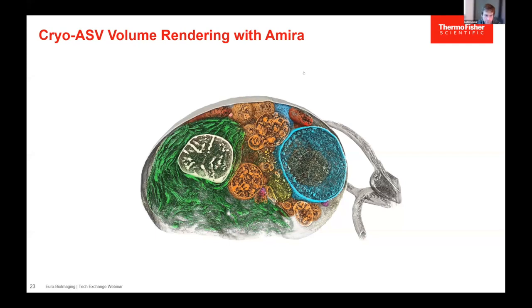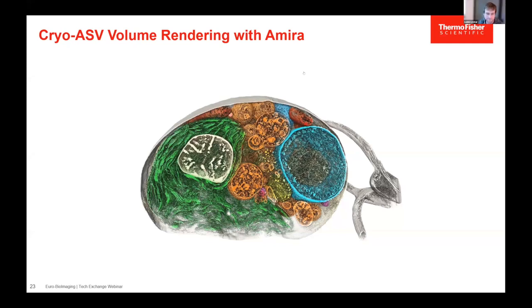A quick follow-up question: what objective is used and what is the numerical aperture? We have a 0.75 numerical aperture objective on the Arctis, and 0.75 on the Aquilos and Hydra systems as well.